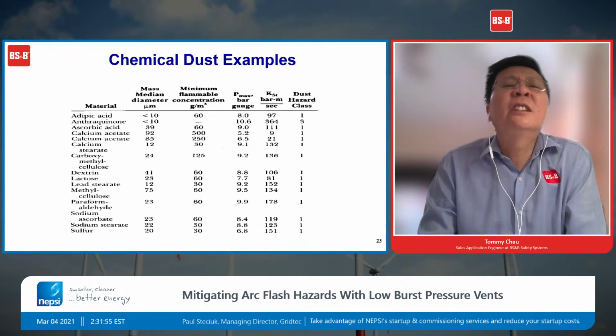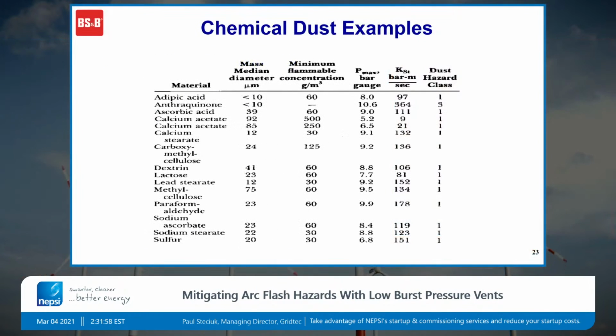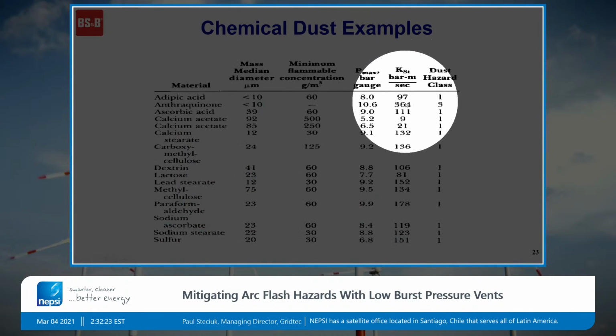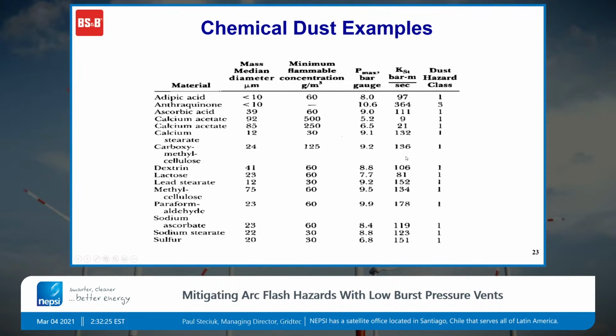And this is a table that provides some examples of KST values for different chemical dusts. As you can see, the very first one has a KST value of 97 and a Pmax of 8 bar. So, the anatomy of the explosion, the Pmax is all the way on the top. It could generate up to 8 bar of pressure. So 8 times 14.5 psi, because 1 bar is 14.5 psi. That could get you up to a little bit over 100 psi.